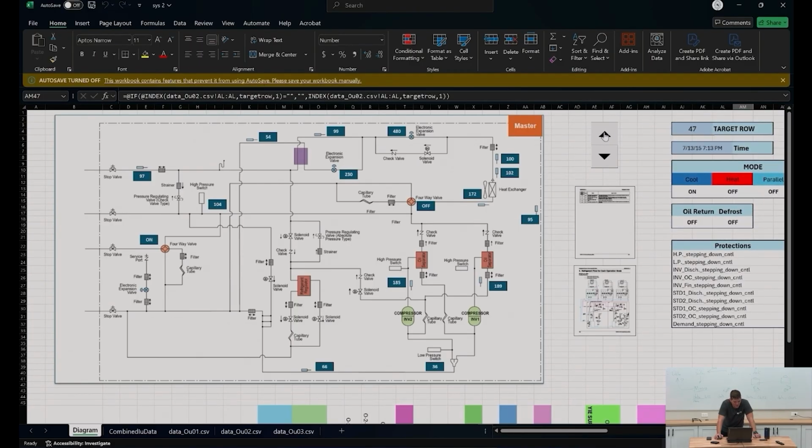But you see how the temperatures on my outdoor unit are changing? Yeah. Or not changing? Changing slowly. Temperatures are changing, valve pulses are changing, discharge temperatures off my compressors are changing, my ambient's staying the same because ambients don't really change drastically over time.